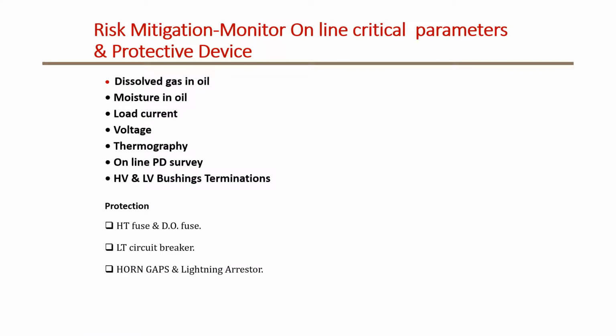Now let's come back to the distribution transformer very quickly. What best can we do for it? At least we can monitor load current and voltage, do thermographic inspection, online PD survey, and very close inspection of terminations, since a lot of termination failures on site are similar for bushing transformers. Any oil leakage can also be physically inspected for distribution transformers.